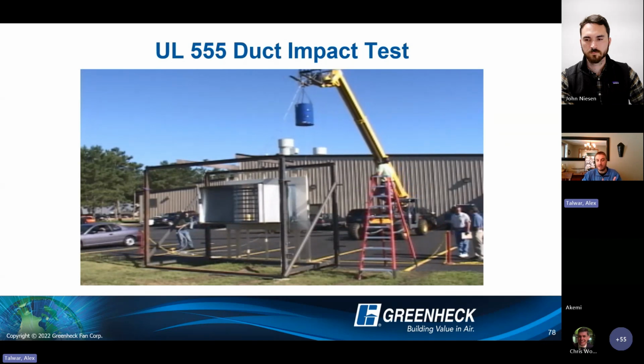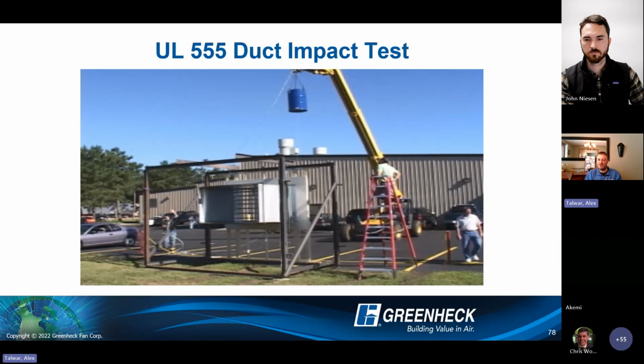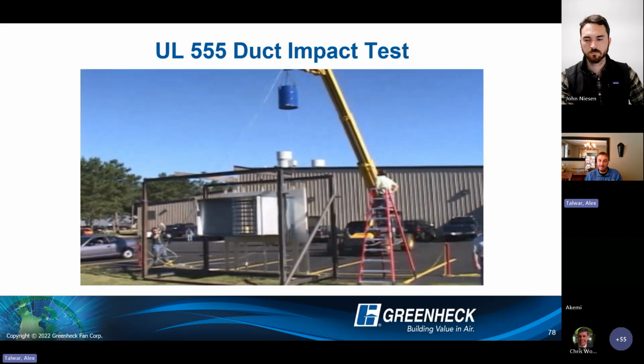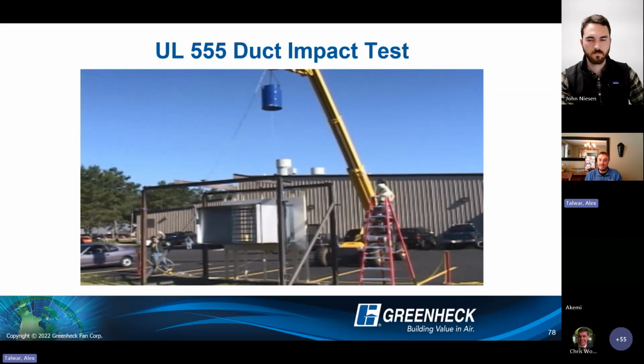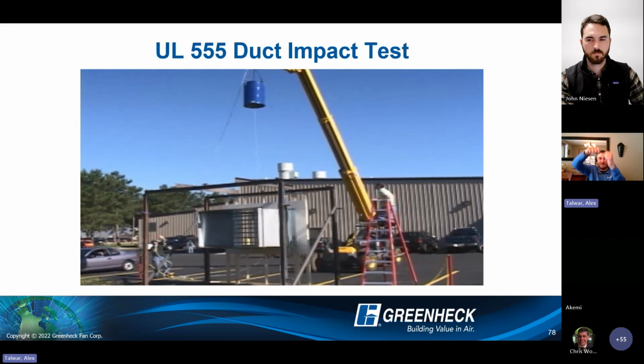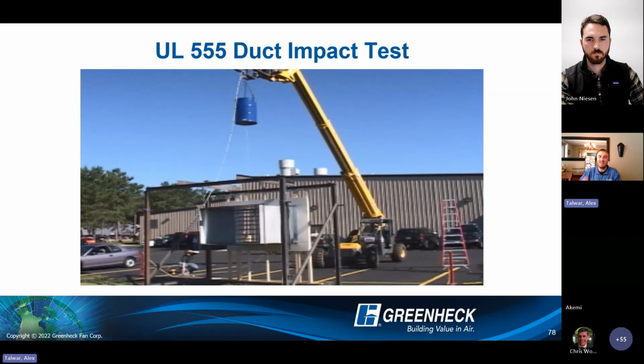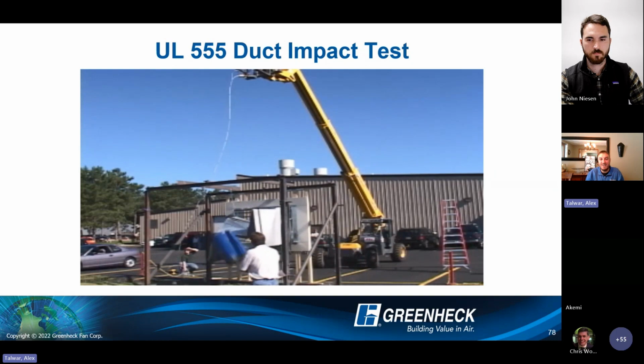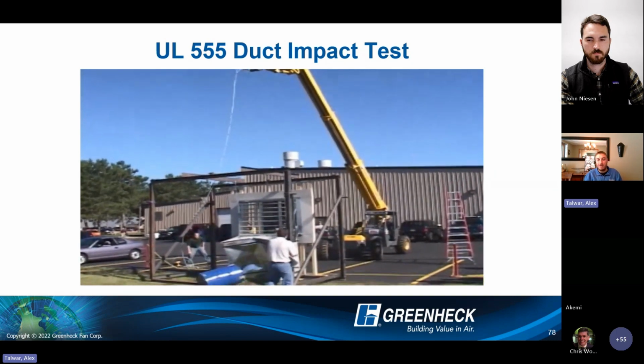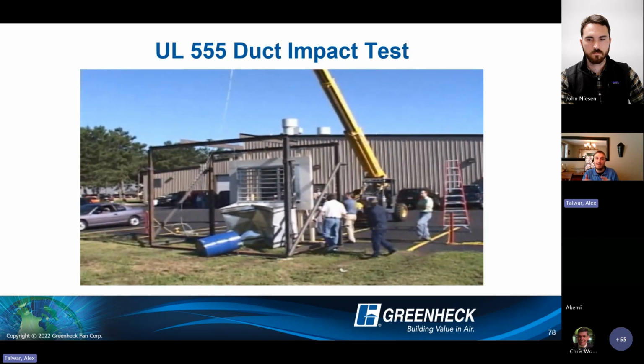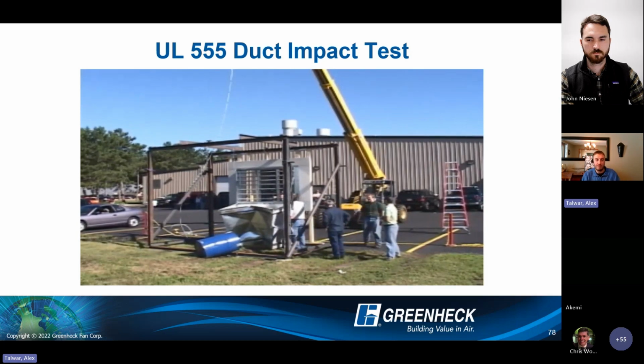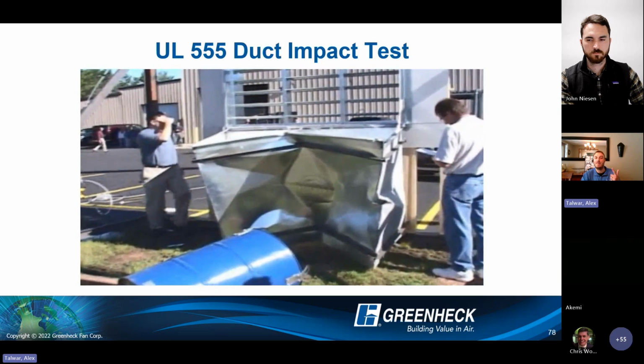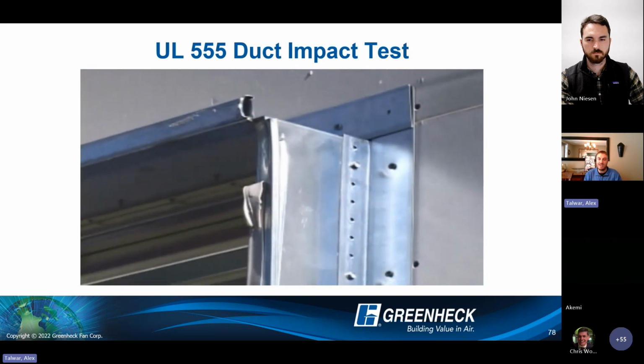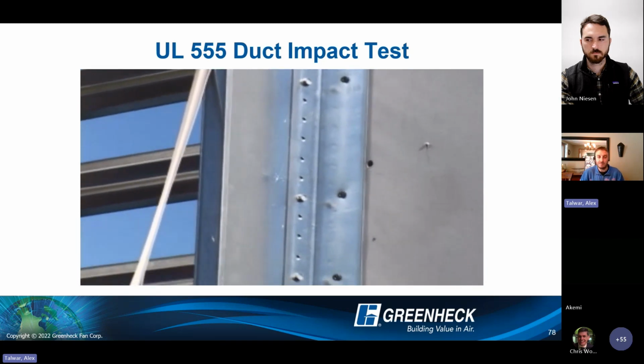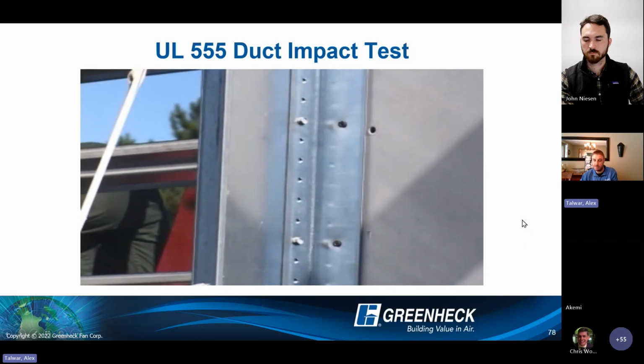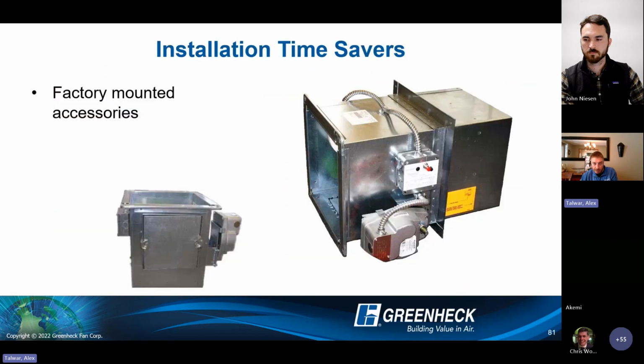And maintain the fire resistance rating of the construction it's installed into. So we have to do this super awesome test where we take a 55-gallon drum, fill it with 400 pounds of sand, and raise it 10 feet above the damper. It's so funny because you're measuring the string with a calibrated tape measure to 10 feet, and then you're just taping it to the bottom of this barrel, dropping it on the duct, and watching the carnage. But ultimately, we're testing to make sure that the installation method is sound, so the damper doesn't come ripping out of the wall, no screws come ripping out, the installation has not been compromised, and the operation of the damper has not been compromised. So that's the purpose of the test. Again, if you do have a catastrophic event, you want these products to remain and provide their protection. So, slow motion video there, the carnage.